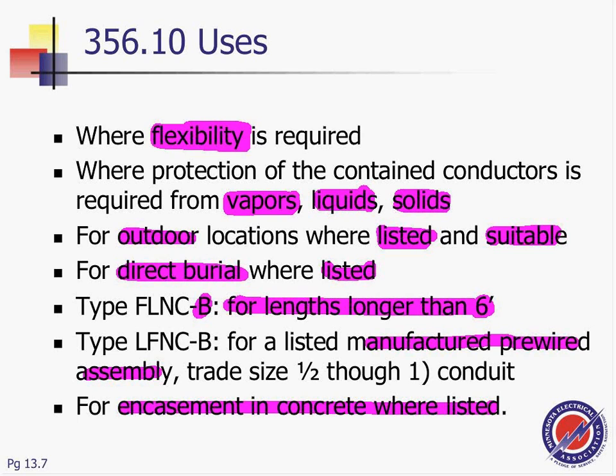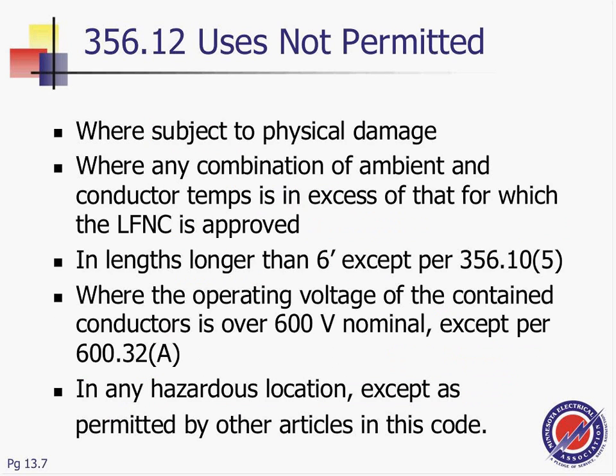The use. So look at the advantage of it. You can direct bury it. You can put it in concrete. You can put it in a wet location or liquid location. And it's good for flexibility. So there are some advantages for using this conduit over the liquid type.